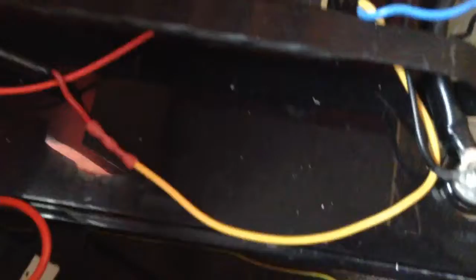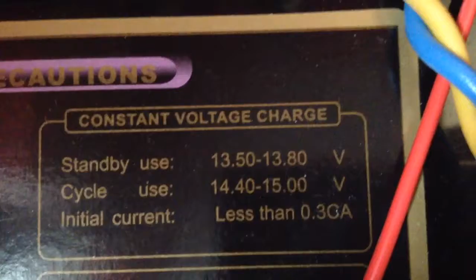If we come down to the batteries, these are the batteries. Okay, I'm just going to show you the label on the batteries, if I can focus the camera. Right, these are Leoch AGM batteries. And here's some charging information. If you're using your system for standby use, that is, you charge the batteries up and you only use them in a power failure, say, then the terminal voltage should be 13.5 to 13.8 volts. So if you have your system as some kind of emergency backup.